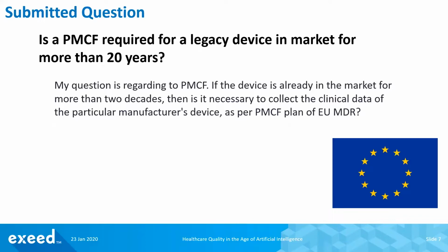Yeah, so what you're saying is that we have a lot of market experience. Do we have to do a clinical study, for example? If you look at EU MDR, they're expecting your PMCF process to be a continual process. They're not mandating you must do X or Y, you define. But let's take the big picture in mind: you have to continually show a favorable benefit risk, correct? So it doesn't matter if your device has been in the market for 2 months or 20 years.